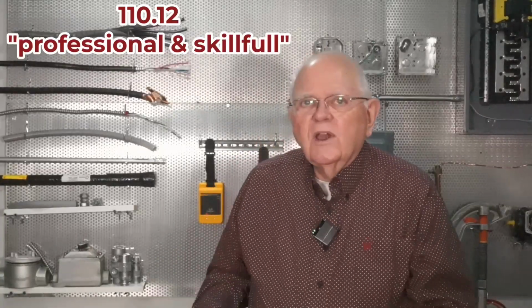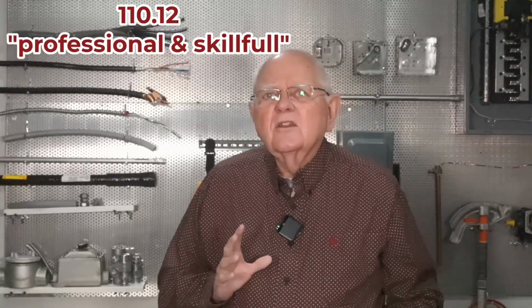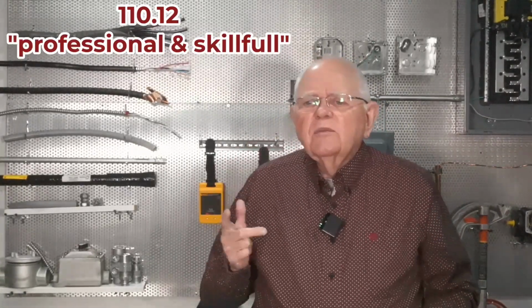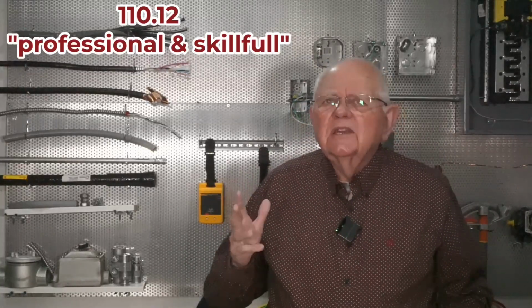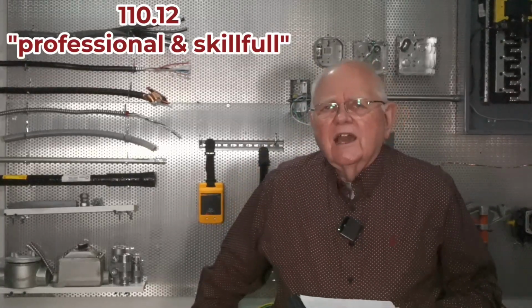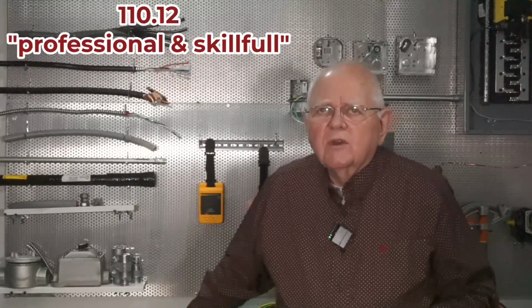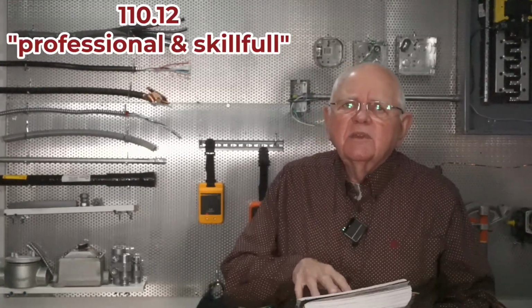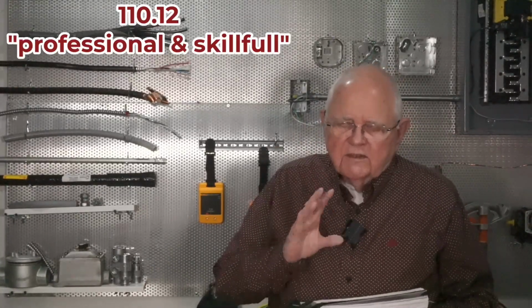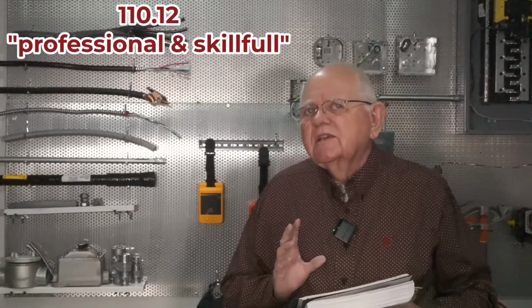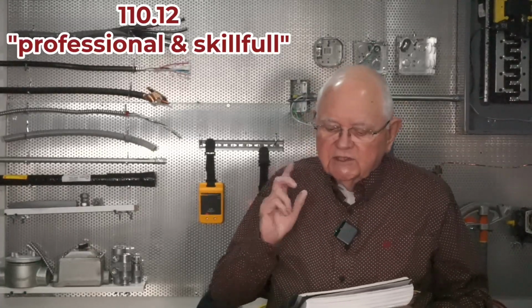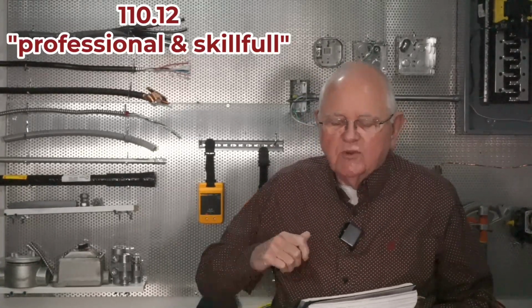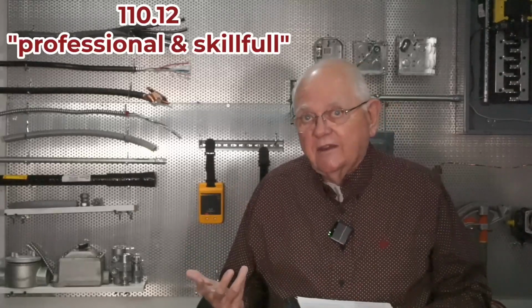Now, 110.12 talks about the mechanical execution of work. If you're familiar with that, for many, many years, it's been in the code for decades, I don't know, 50, 60 years or more, and it always said it had to be done in a neat and workmanlike manner. That wording changed with the 2023 edition of the code, and now it says electrical equipment shall be installed in a professional and skillful manner.